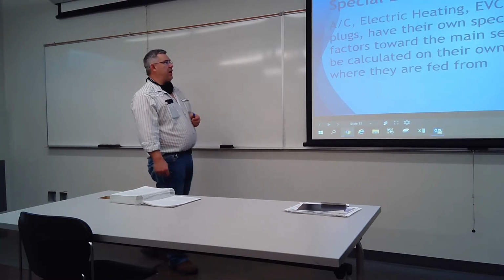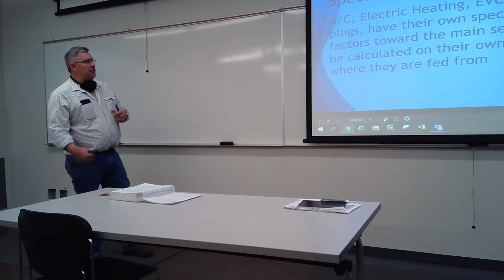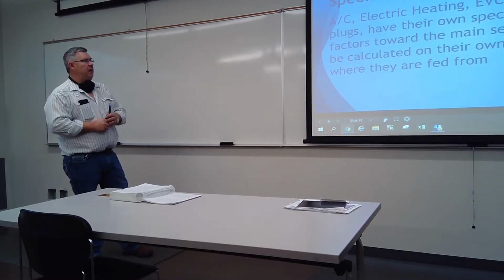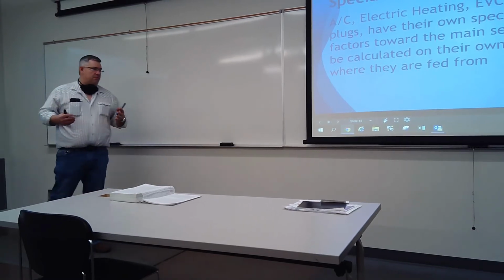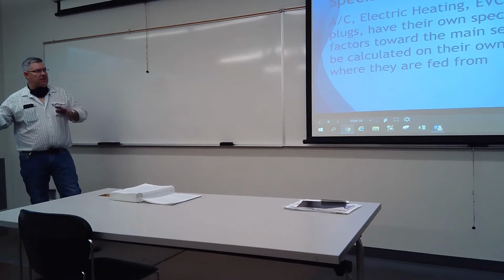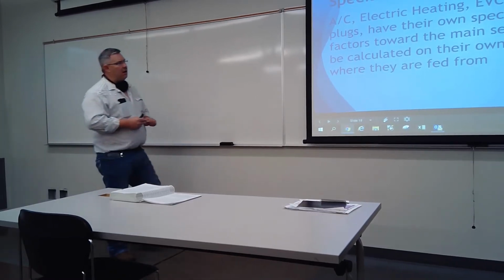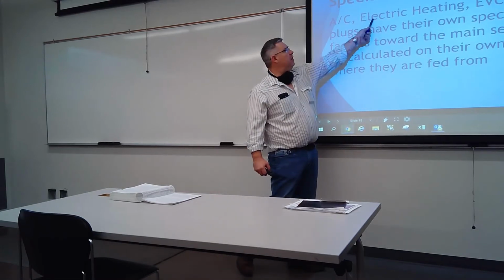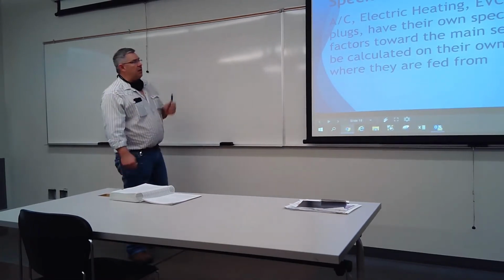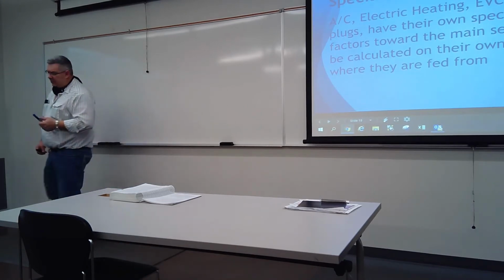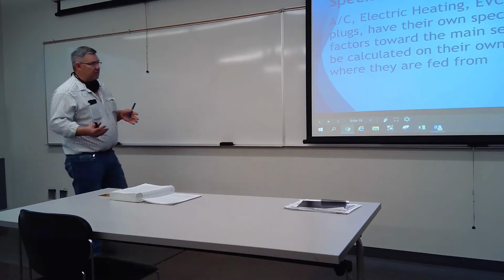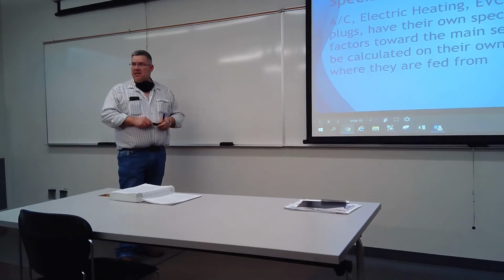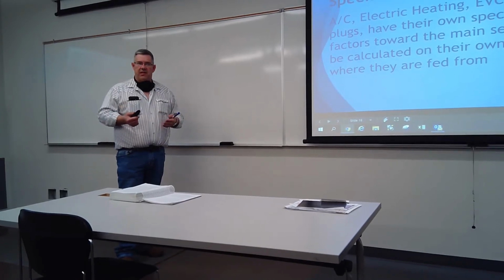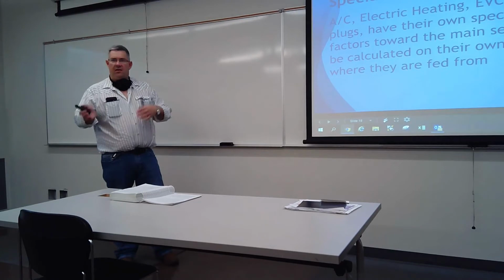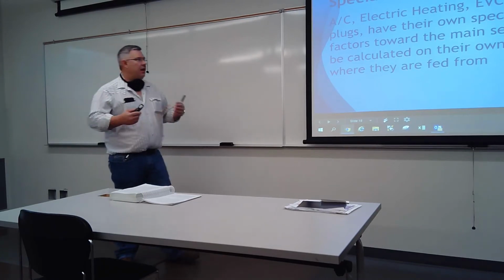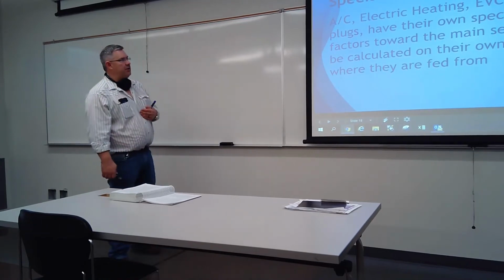Air conditioning, electric heating, electrical vehicle chargers, and parking lots all have their own special demand, so we still treat those a little bit differently. Electric heating is what catches a lot of people. When we looked at it doing single dwelling calculations, if you read 62-118, it talks about electric space heating with individual thermostats located within dwelling units. And you took the first 10 kilowatts at 100%, and everything above the 10 kilowatts at 75%.